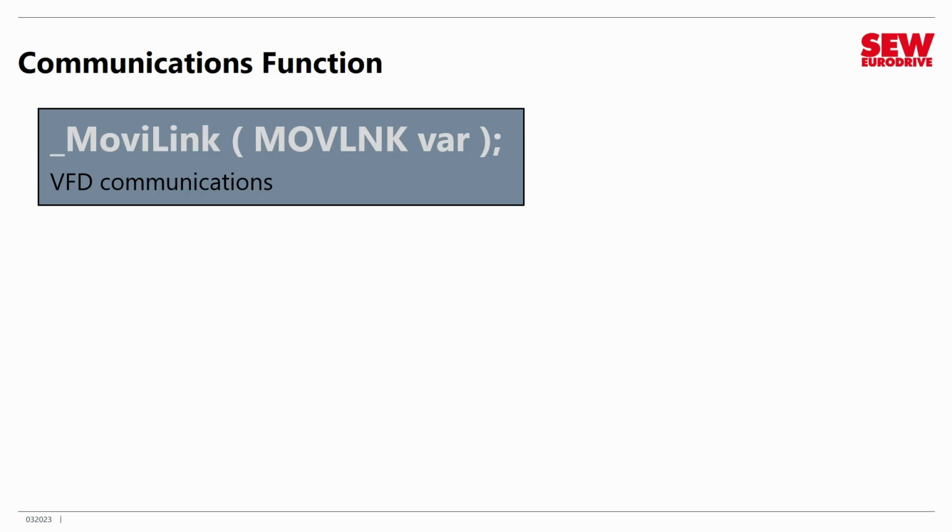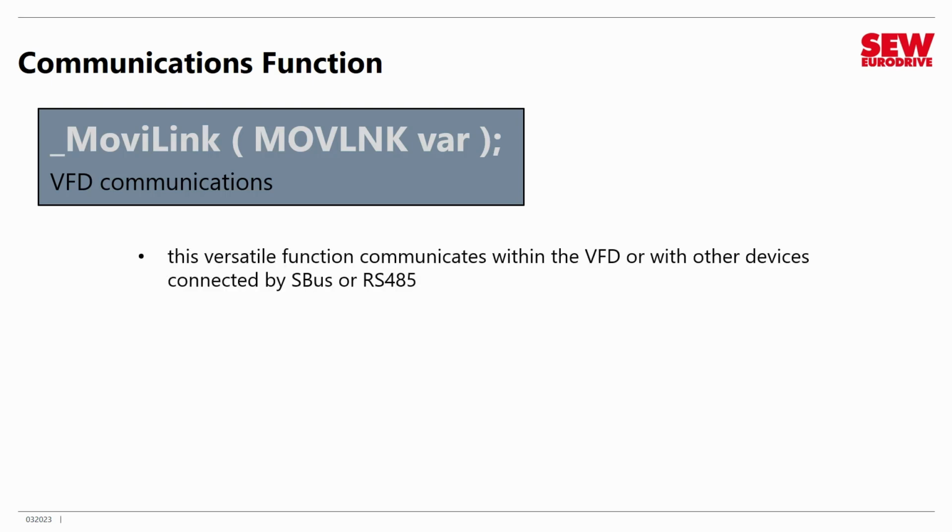So you might be inclined to think, okay, this makes sense. This is for VFD to VFD communications. And the answer is, yes, it certainly is, but it's more than that. This versatile function can not only communicate across the S-bus or RS-485, it can actually communicate internally within the VFD as well. And that's kind of what makes this function a little weird to my mind.